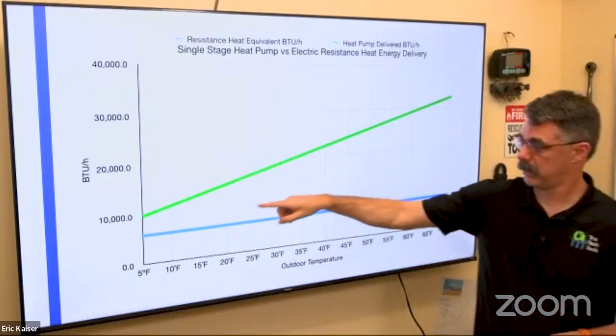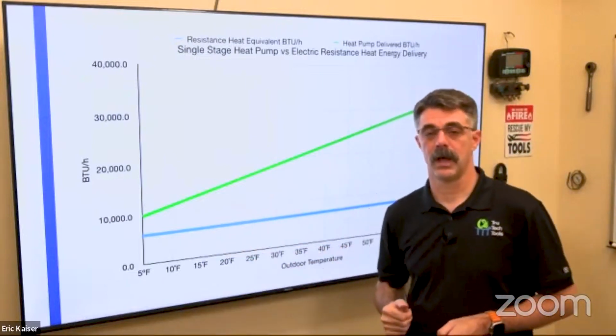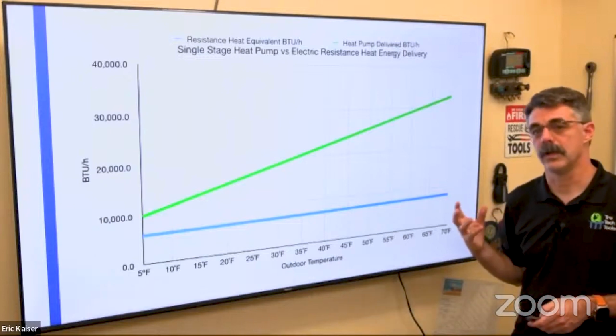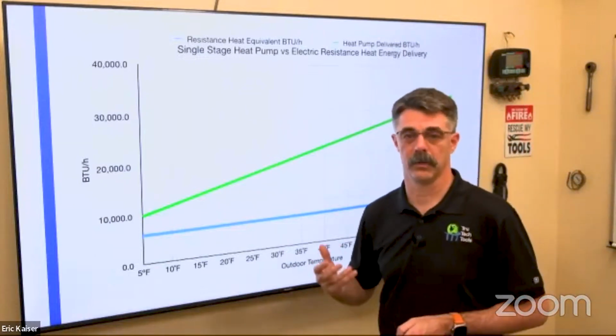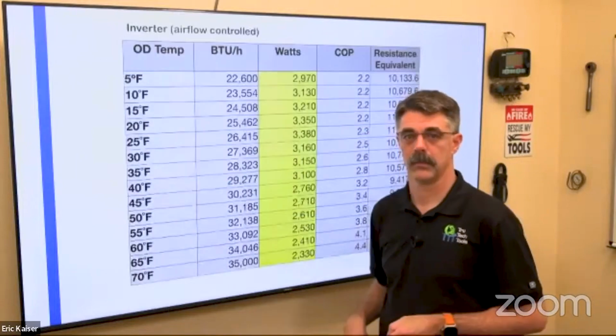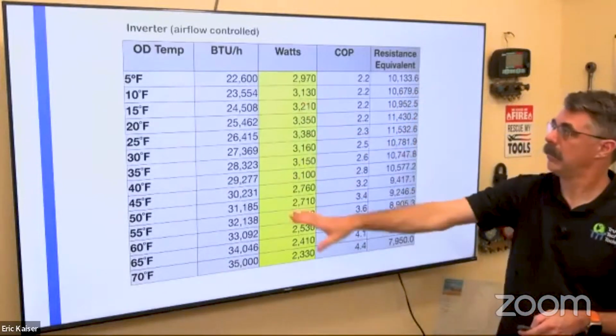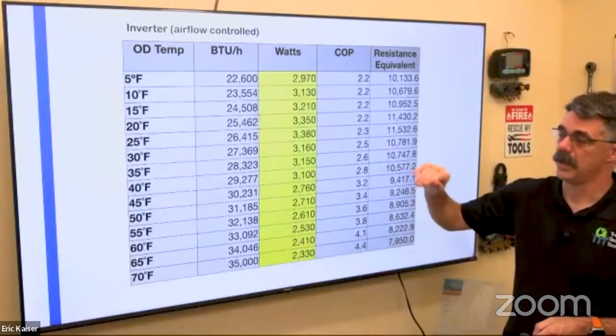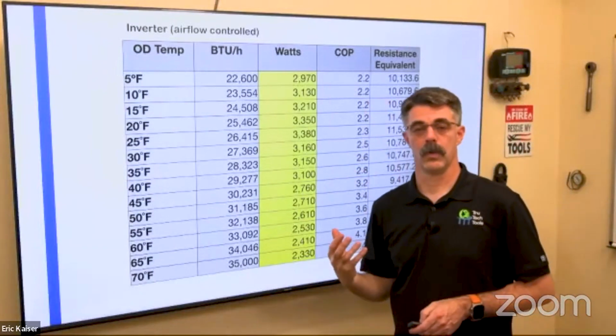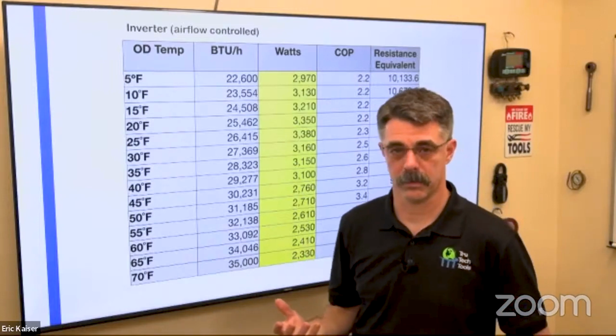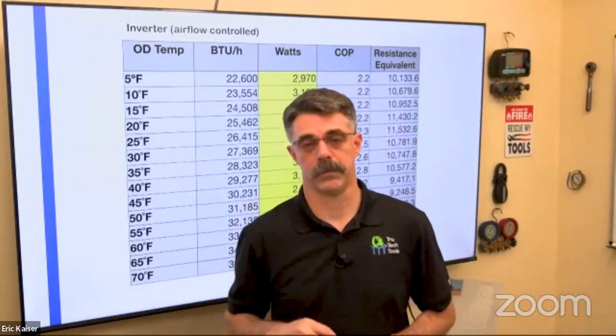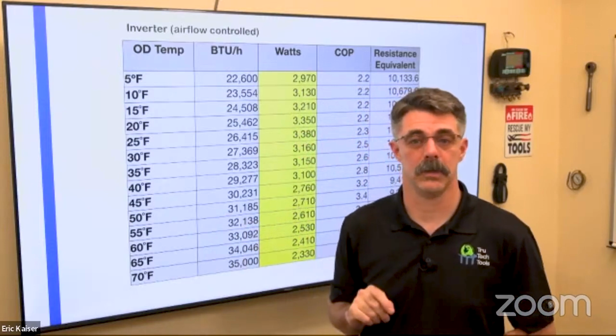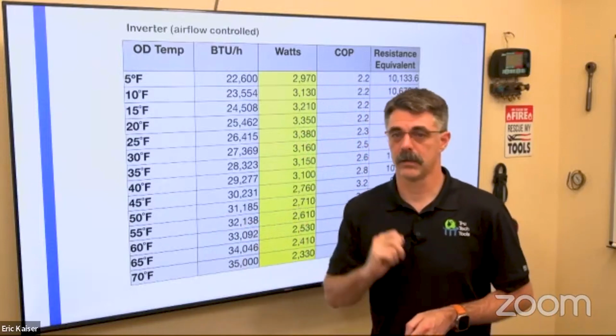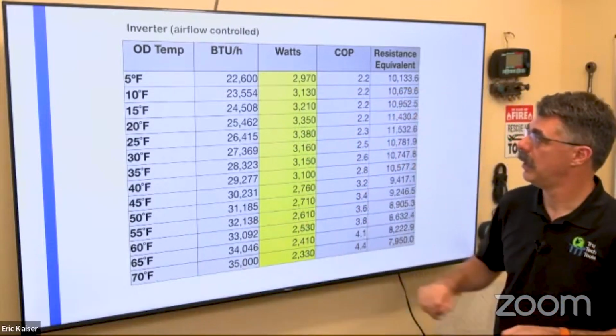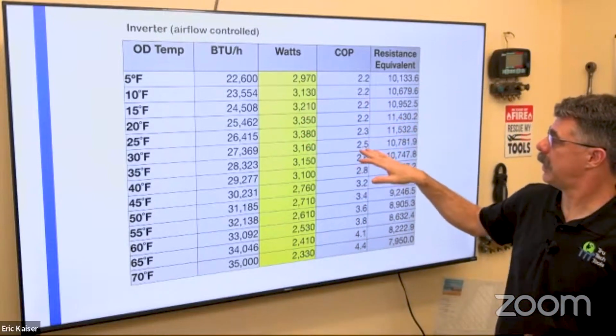As long as the green line's above the blue line, I'm better off running the heat pump, because it's going to use less energy, therefore costing my customer less. Same kind of data, right? Except this is what's called an airflow controlled inverter, where we control the compressor speed of an inverter compressor by changing the airflow indoors. So there's no communication between the indoor and outdoor unit. There's just standard conventional thermostat wires, right? But being as it's an inverter, it carries that 2.2 all the way down at 5 degrees.